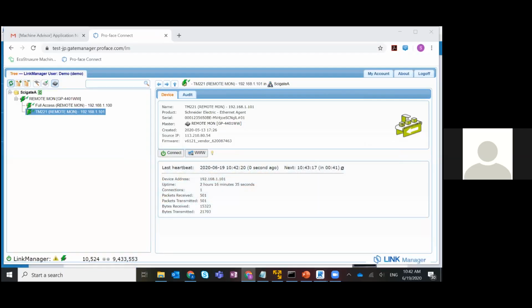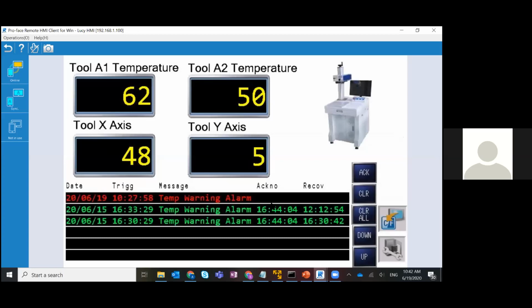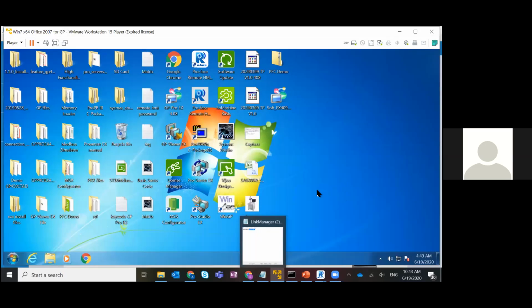Based on the HMI screen, it shows a temperature warning. I know the temperature probe is connected to the PLC, and the PLC is sending this alarm to the HMI. So looking at the HMI screen, you can identify some of the first layer issues at hand, but if you want to go deeper, you might need to connect to the PLC instead. Let me show you how I connect to the PLC.